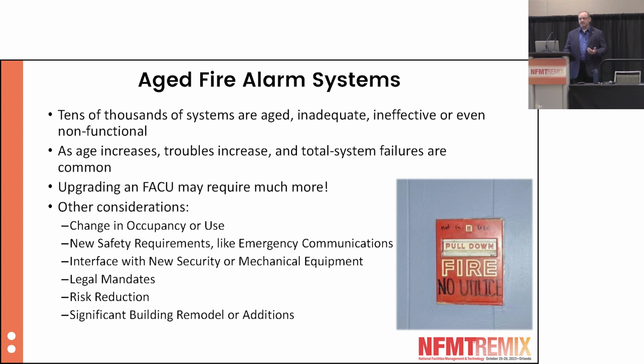We have situations like active shooter events, severe weather, and other events where we need to communicate information to building occupants, but our existing fire alarm systems may not have that ability. When interfacing with other equipment in a remodeled building, like new security or access control features, mechanical equipment, or elevators, does your existing fire alarm system have the ability to communicate or handle this newer technology? We might also have legal mandates placed on a facility based on the type of tenants in the building.